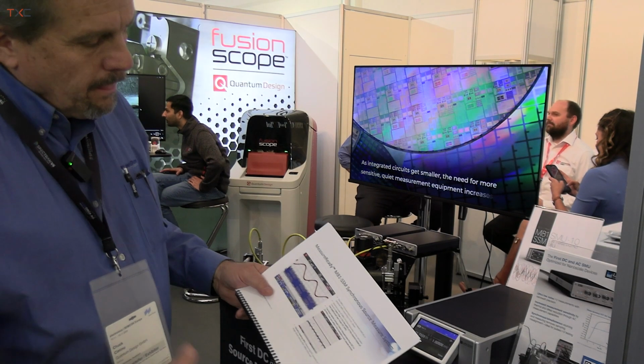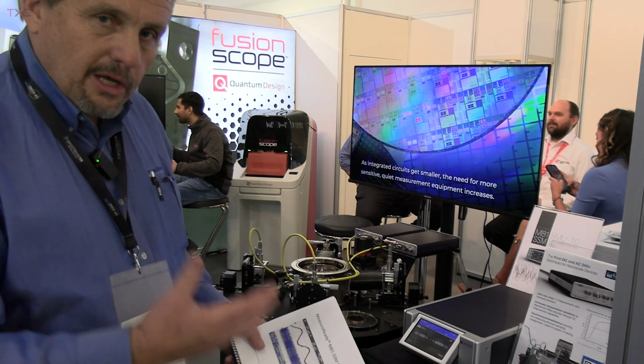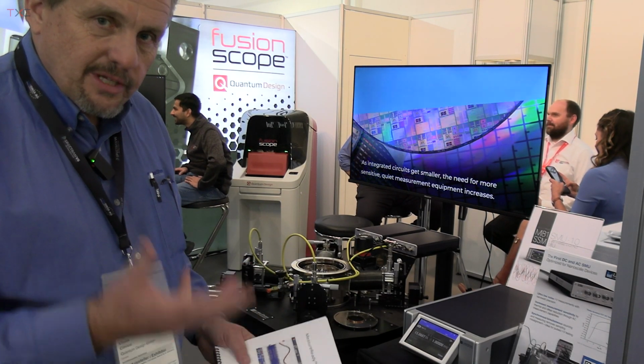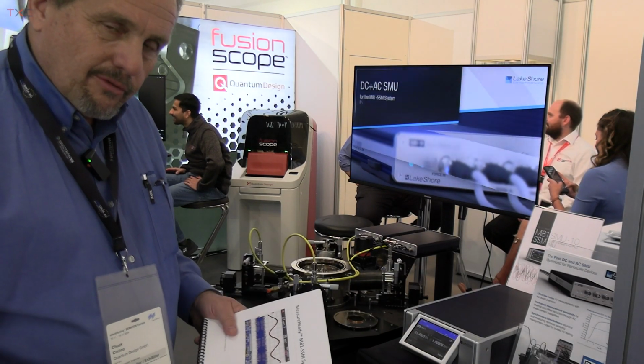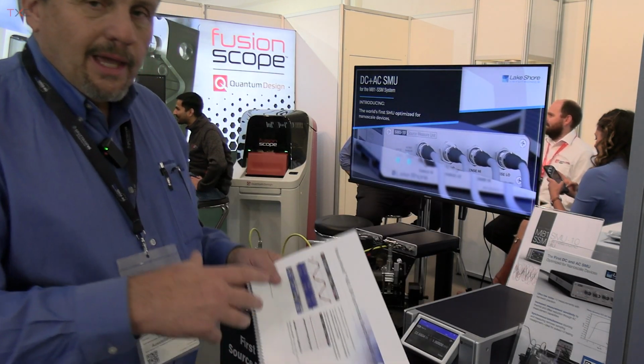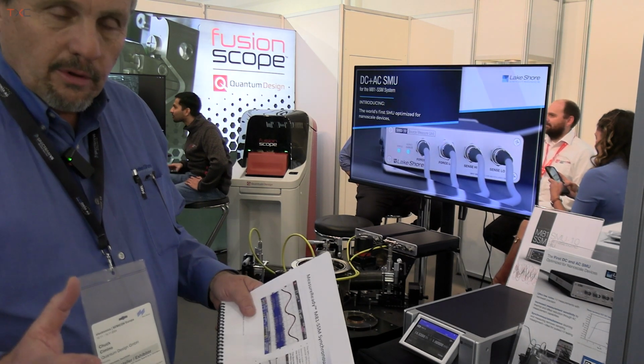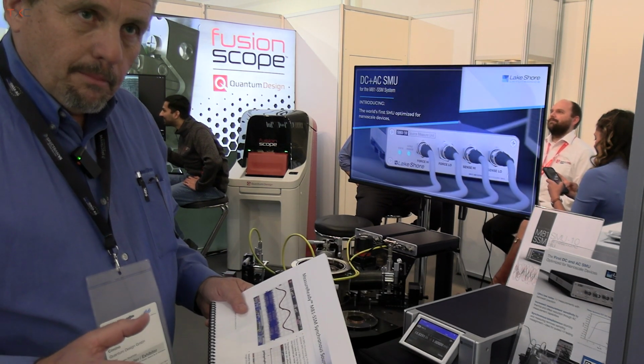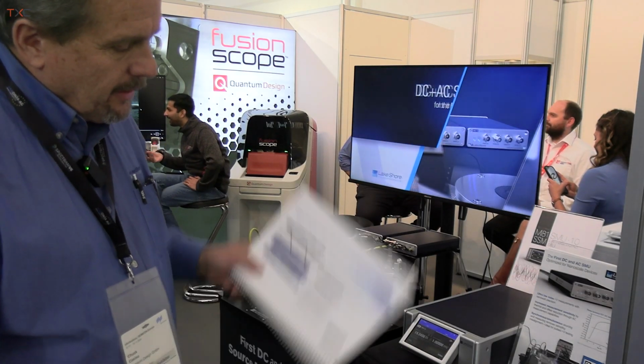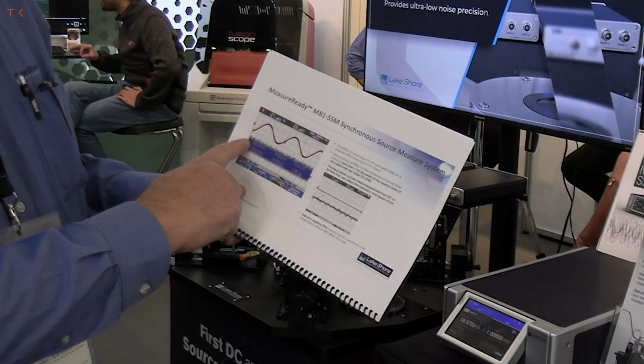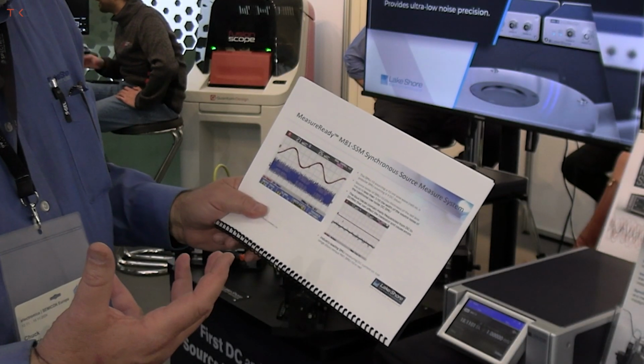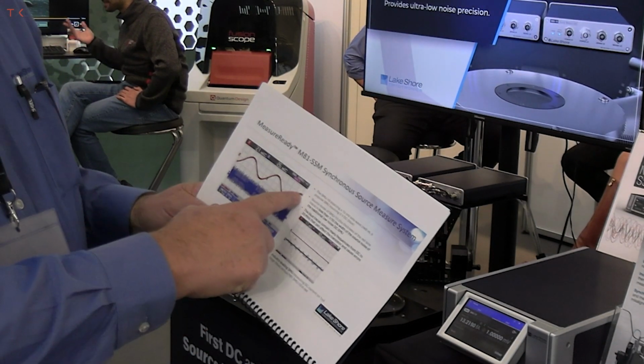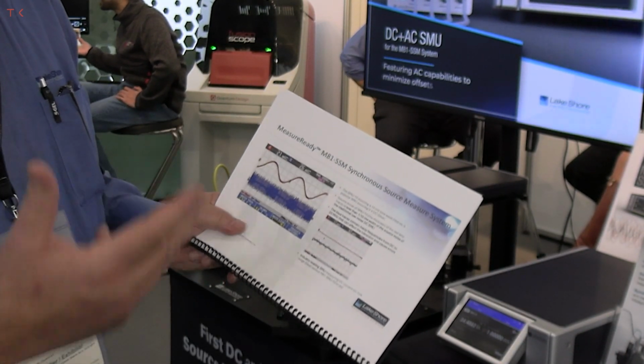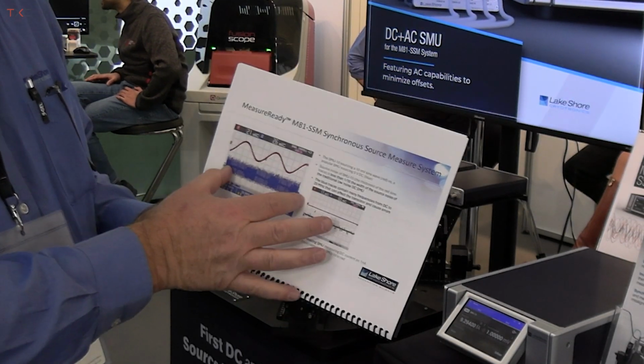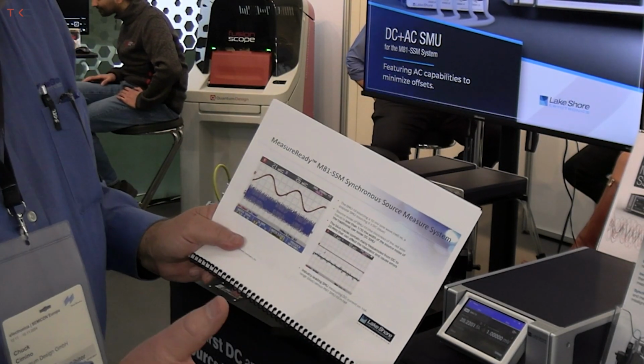Here's an example. We've architected this system for the lowest possible source noise and the highest possible sensitivity both. When you're making low-level measurements, you have to worry about the noise of your source and the sensitivity of your detector both. Having one or the other, but not both, is problematic. Here's an example of a very low noise DC SMU instrument versus our SMU instrument. You can see the thickness of the blue line versus the thickness of the red line is roughly 100 times lower noise. And this is 0 to 20 megahertz, so-called wideband noise.